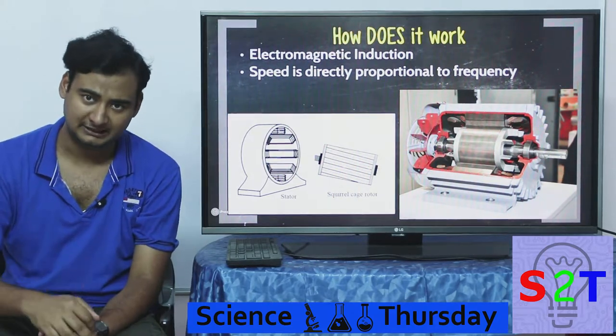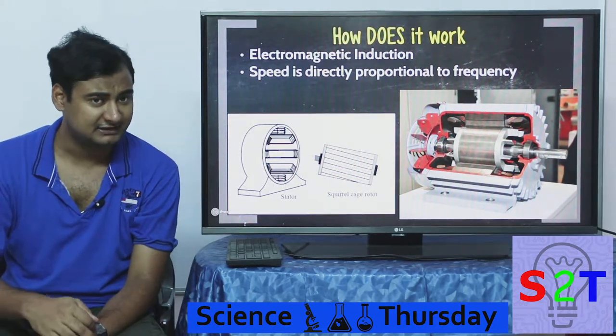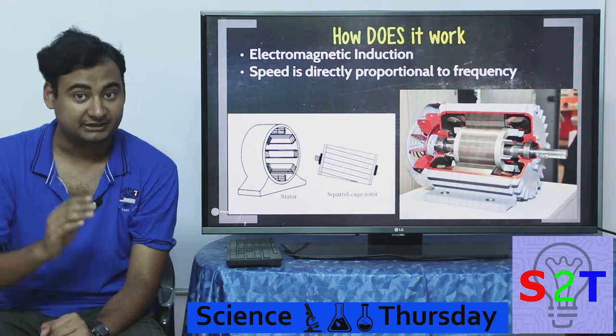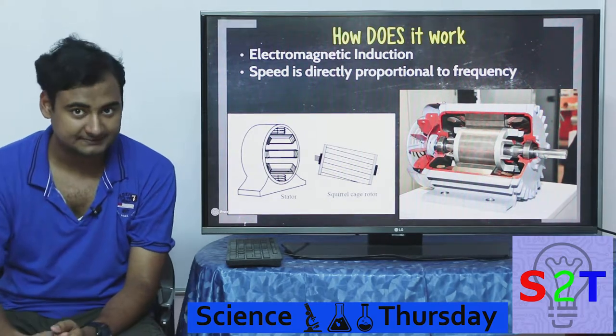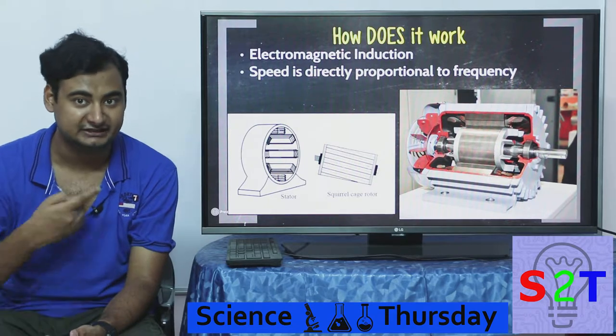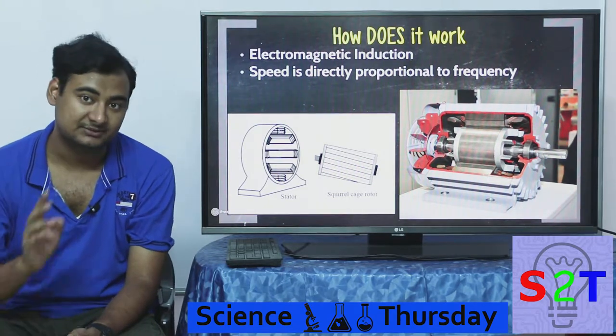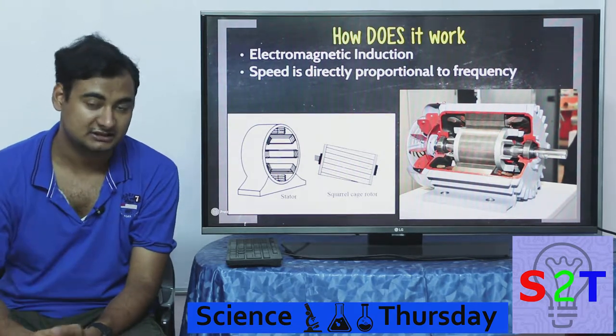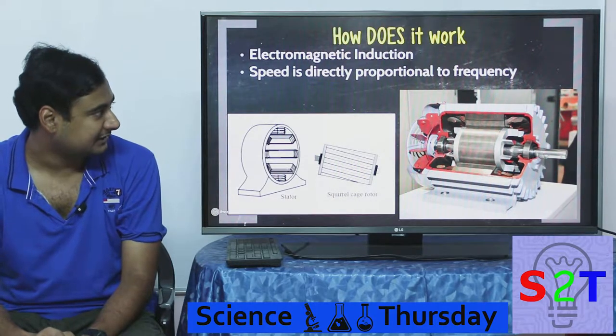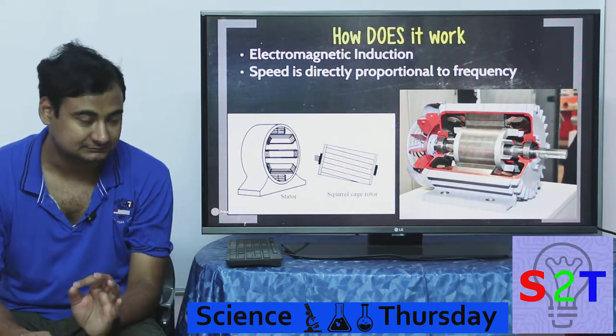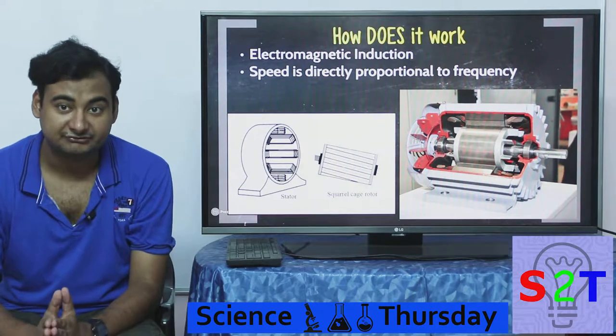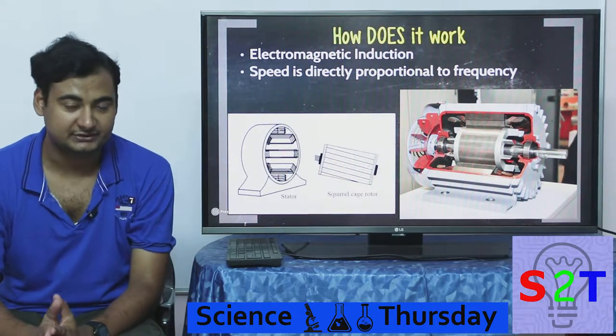Now if you have a single-phase motor you have to have a capacitor to help it start, otherwise it won't rotate — it will just keep vibrating and oscillating. But if you have three-phase or even two-phase, it has a continuous rotating magnetic field, so you don't need any starter. That's why Nikola Tesla made a two-phase motor.